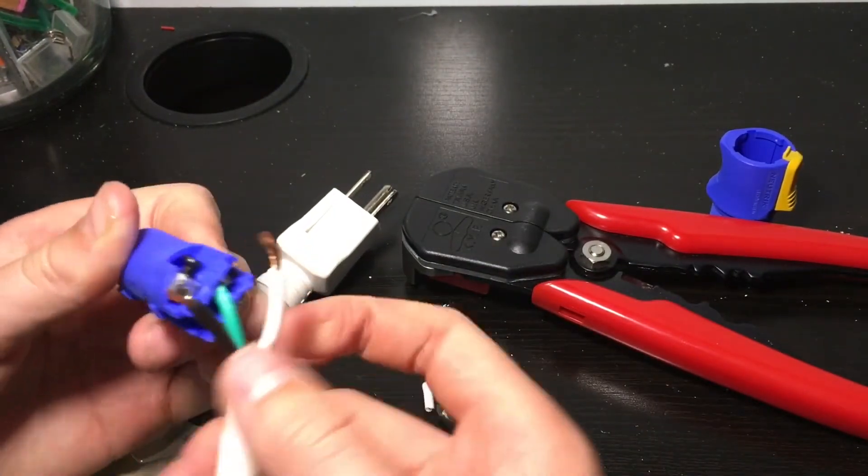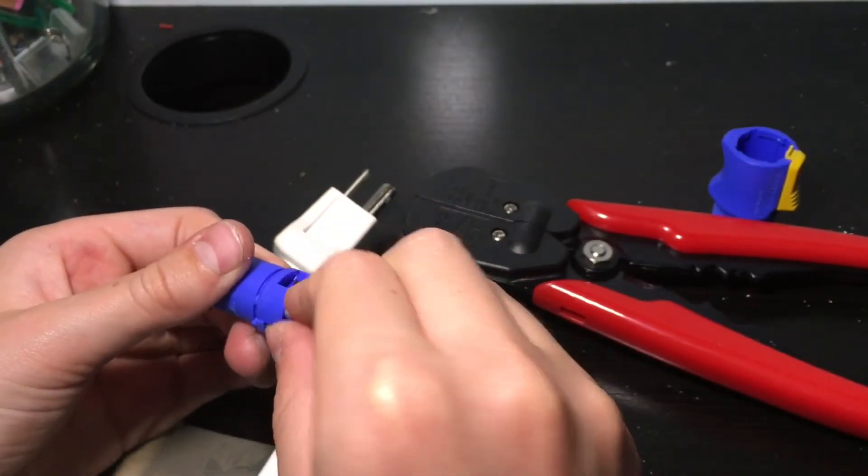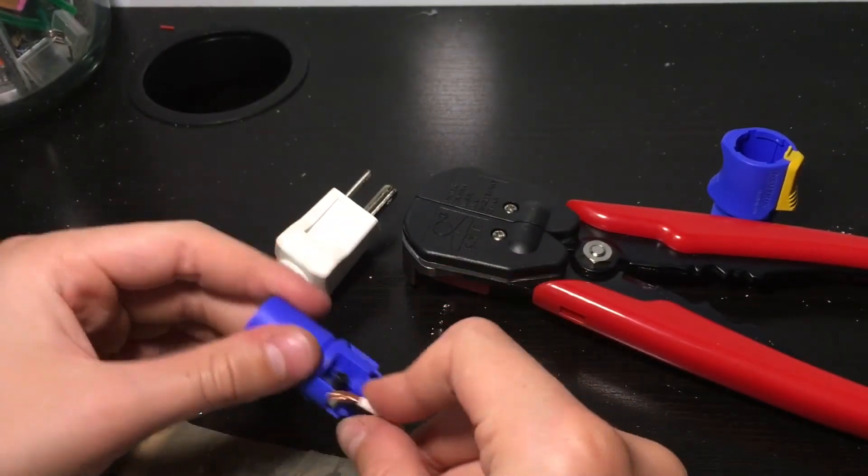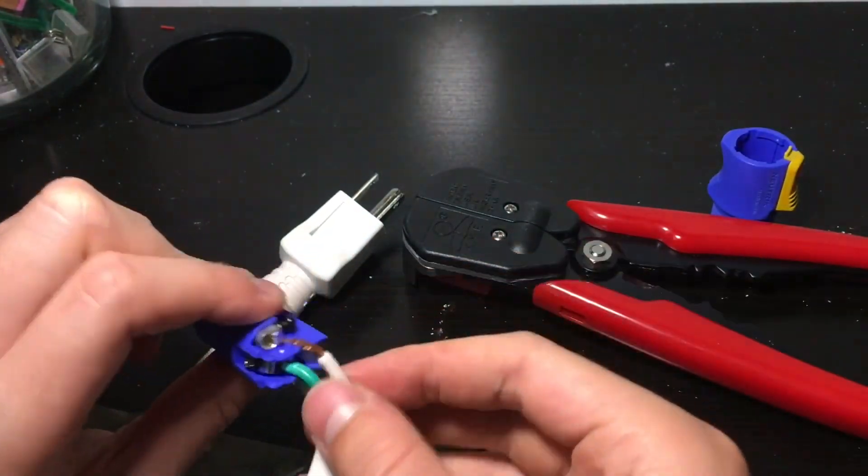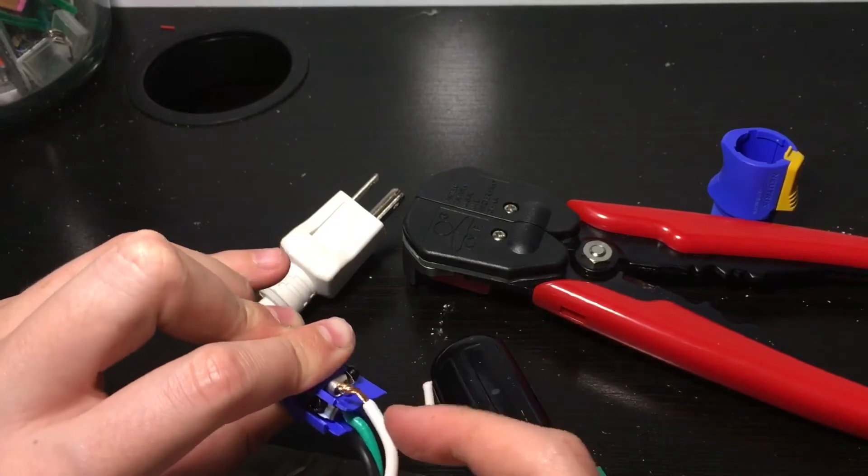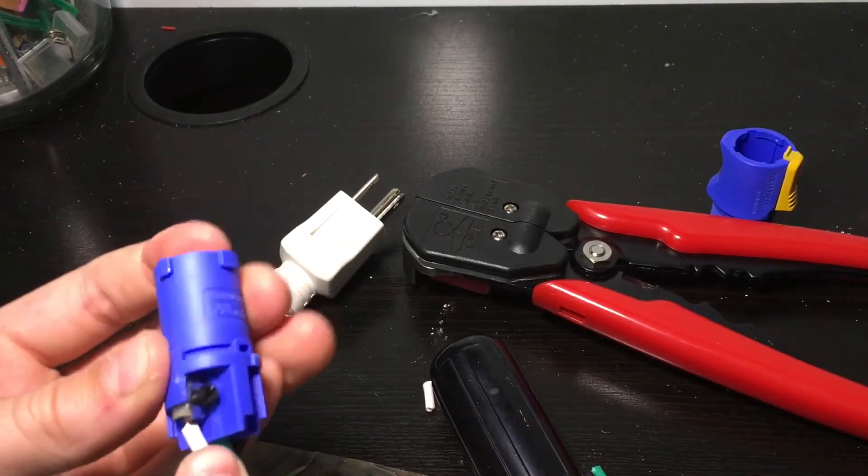Then do your next one. You're going to put black into the one that has the L, and then screw that down. We can assume by process of elimination that the last one, the white cable, goes into neutral.